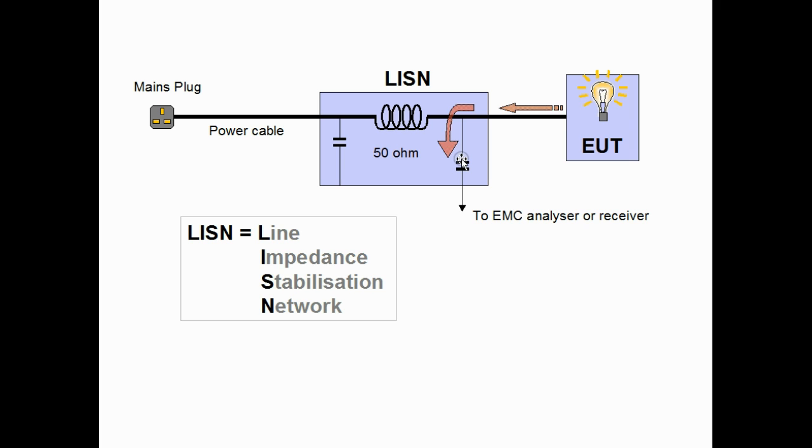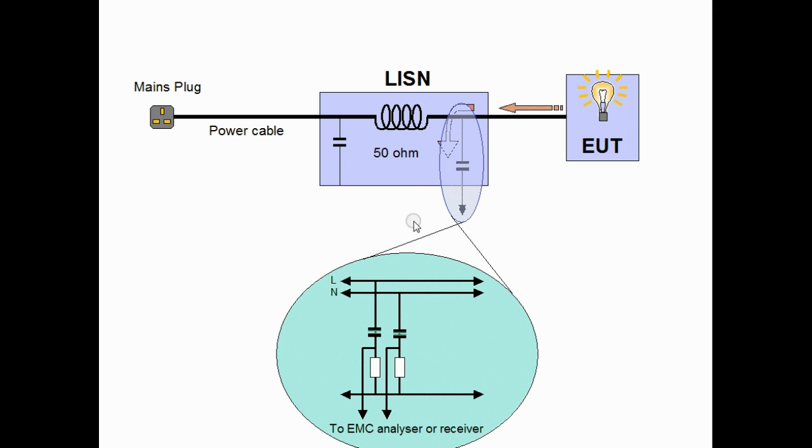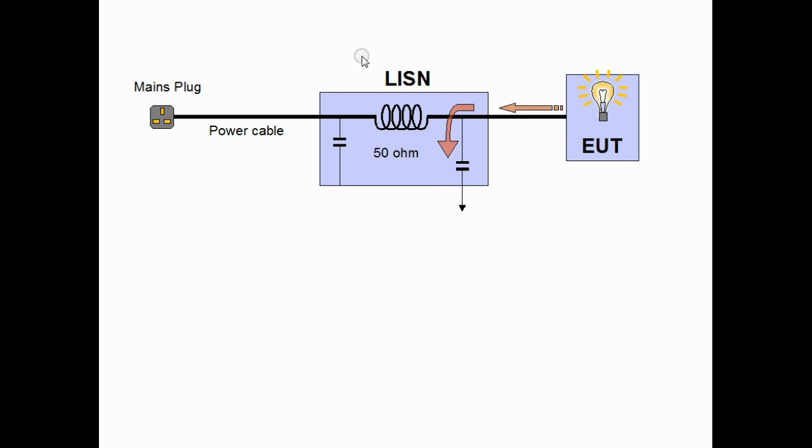If we look in more detail at how we connect to the line, we can see that we need to connect to both live and neutral on a single phase supply. These are each measured by the analyzer, each must comply with the limit set down by the standards. Similarly, in a three phase supply we have four connections and we measure each one in turn. So that's how a LISN works.